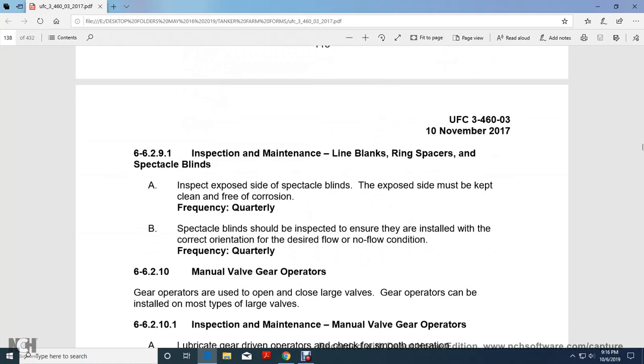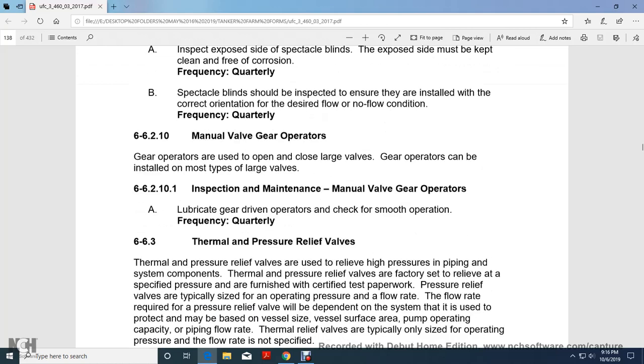Inspection of line blanks, ring spacers and spectacle blinds. Any exposed side of the spectacle blind must be kept free of corrosion, checked quarterly. Spectacle blinds should be inspected to ensure that they are installed with the correct orientation for the desired flow and non-flow condition. Manual valve gear operators.